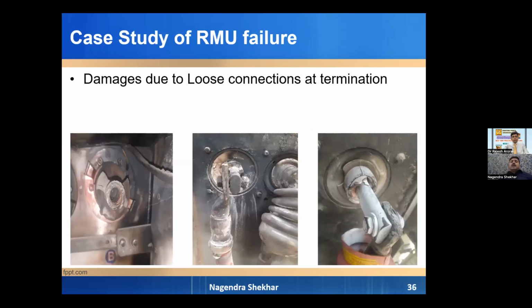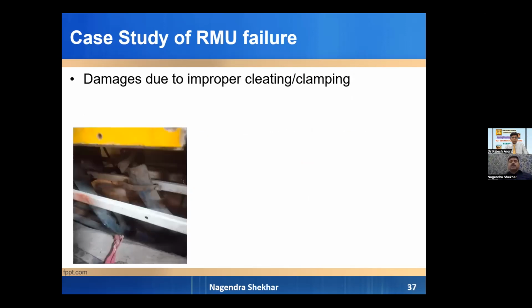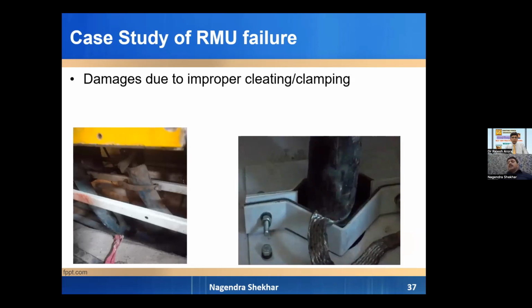So these are a few examples. Because of loose connections, cracking or continuous sparking, heating of our metallic parts results in failure of epoxy bushings or porcelain bushings. These are very common issues when the connections are not done properly or proper washers are not used. The cleat is there, the clamp is there, but the cable is not of that particular size. So it is an oversized clamp, and the load of the entire cable is on the bushing. You can see it in both the cases.